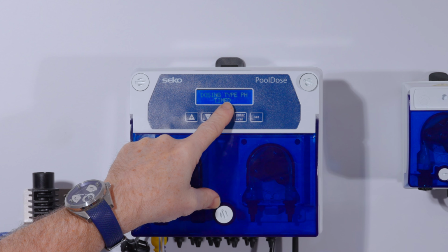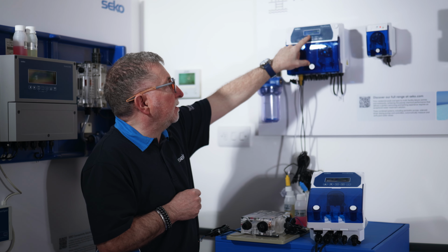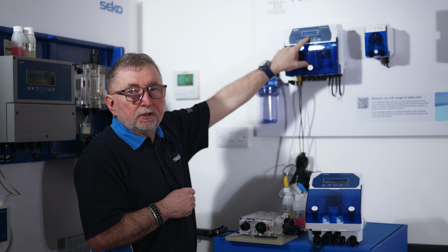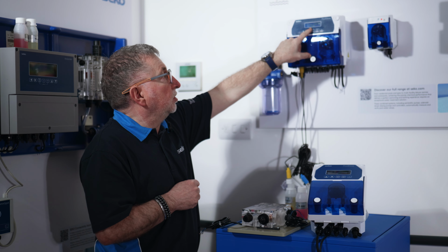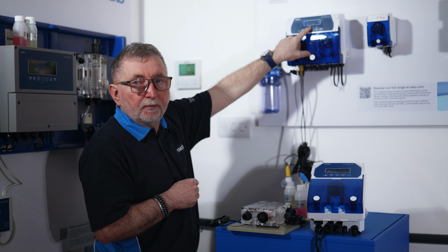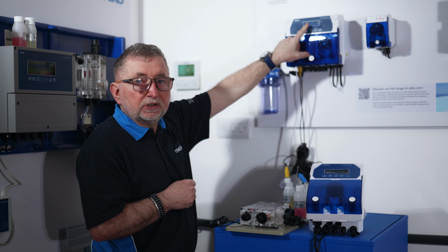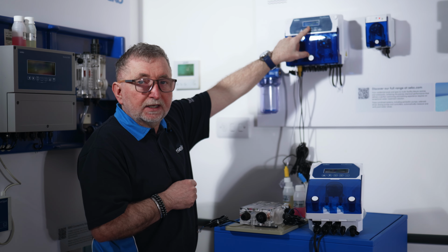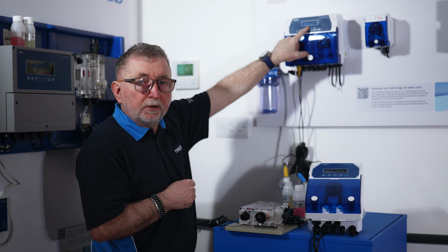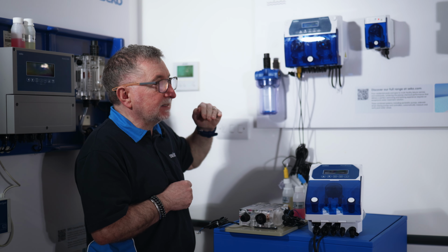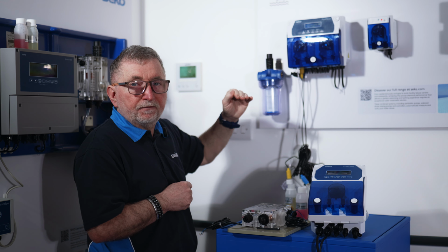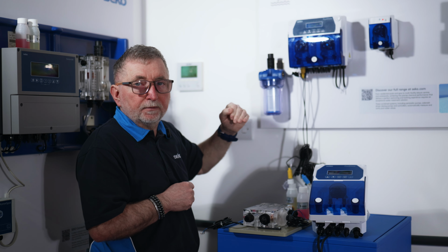This is the dosing type. For pH, we currently have this in timed, and in this mode, when you set the settings for the pH, you will get the options to select a time on and a time off. If you select proportional mode, these settings are fixed. Proportional mode means that the unit will automatically run the pump for longer, the further away from the set point you get. This is the same for the ORP or redox.